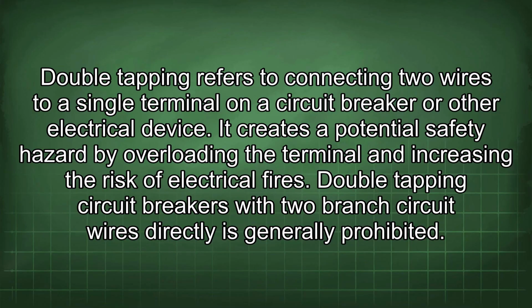Double tapping refers to connecting two wires to a single terminal on a circuit breaker or other electrical device. It creates a potential safety hazard by overloading the terminal and increasing the risk of electrical fires. Double tapping circuit breakers with two branch circuit wires directly is generally prohibited.